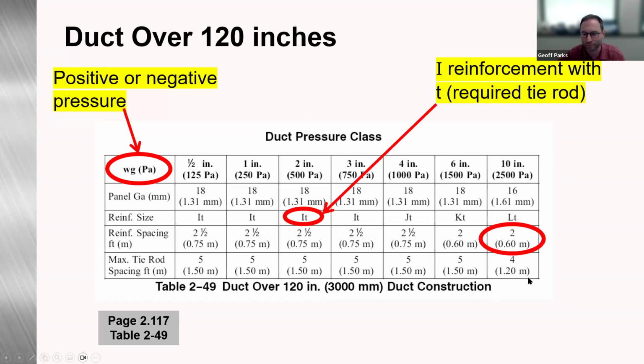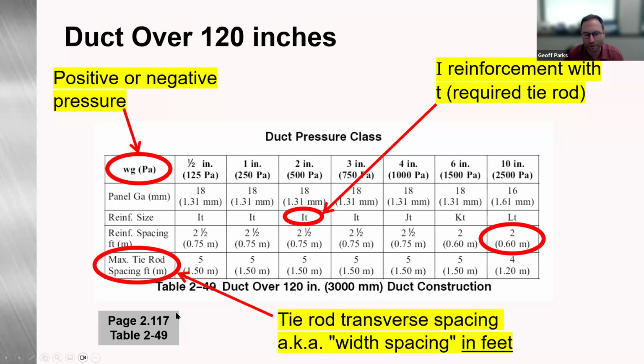So that's reinforcement spacings, 2.5 feet to 2 feet. And then our max tie rod spacing. If it's telling you 5 foot is your max tie rod spacing, you would take the width of your duct and divide it by 5 feet, and that'll tell you how many tie rods are required for that duct size.